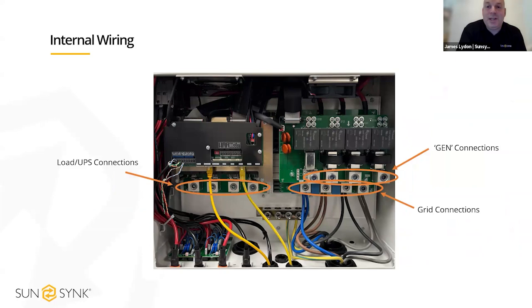Okay, this shows you the 50 kilowatt with the covers off. You can see we've got 3 different connections there. The top right one is the generator input. Our generator input port will do one of 3 things, but it can only do one of them at once. It's either your generator input, or we can program it as a diverter output, which works similar to your eddi and your iBoost, or we can have it as a physical AC coupled input. Earlier we were speaking about AC coupled systems.